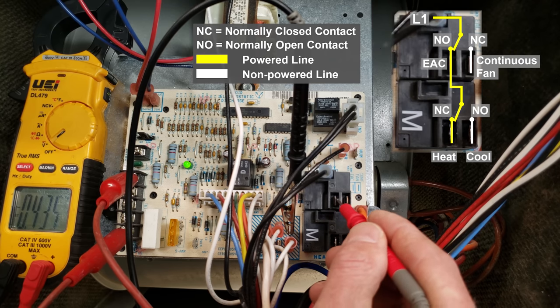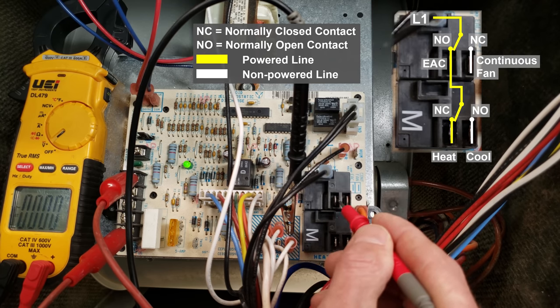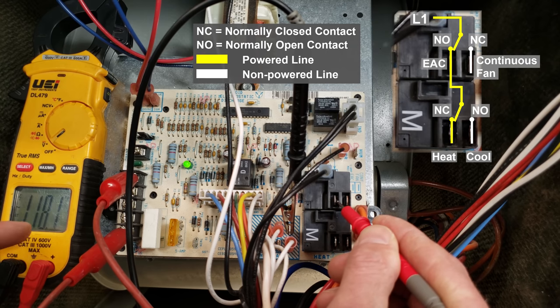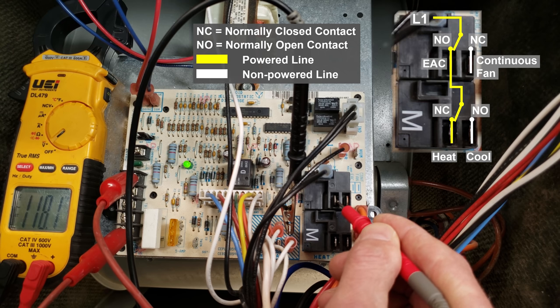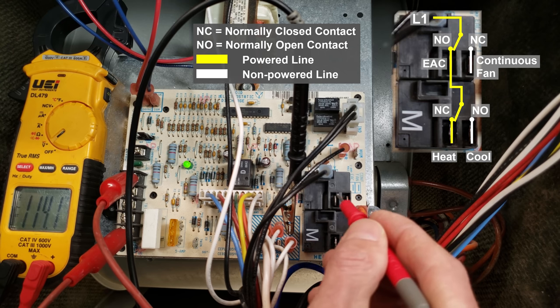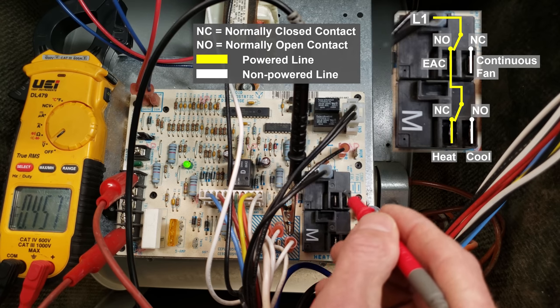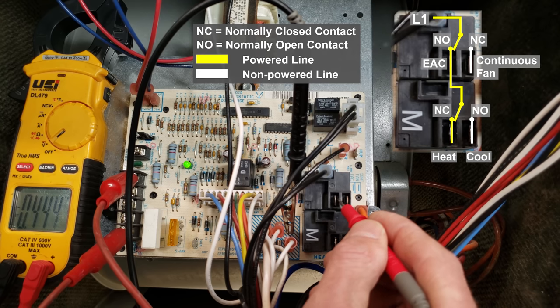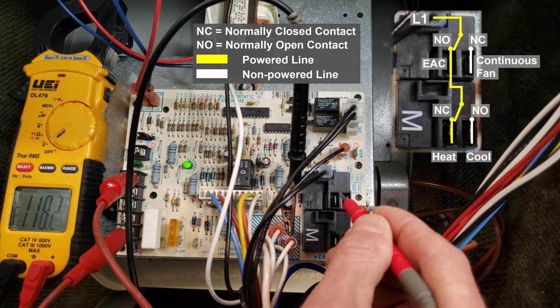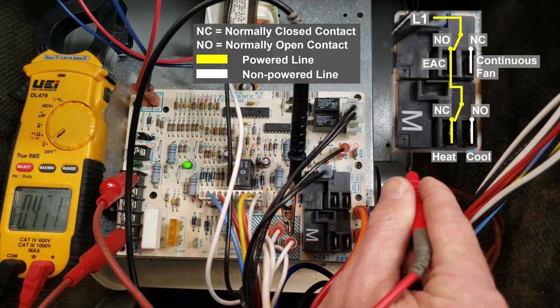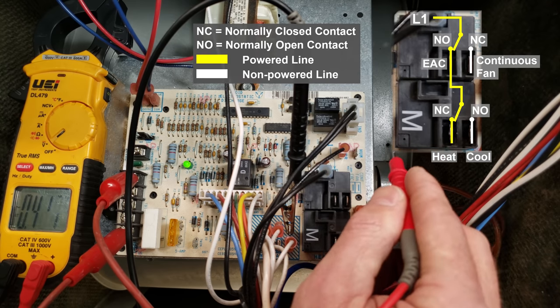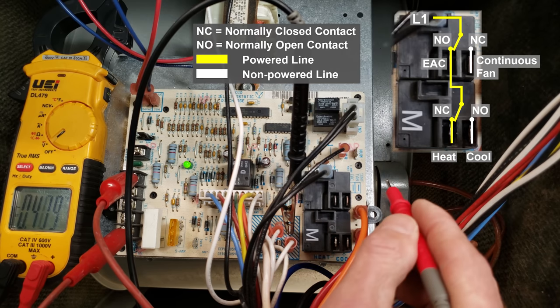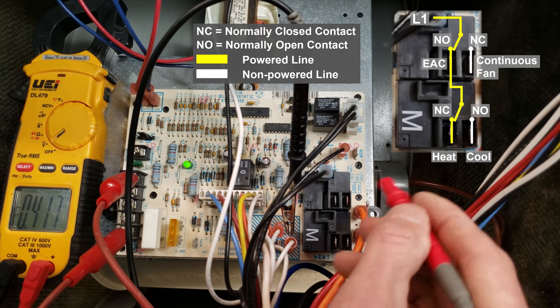Right now your main power is connected over to EAC as you can measure and see with the multimeter, 118 volts. I also want to point out that if you have an electronic air cleaner you would connect it right here because this terminal is not going to get powered until the blower motor is going to be running. So you don't want to have the electronic air cleaner running all the time, you only want it to run anytime the blower motor is running.